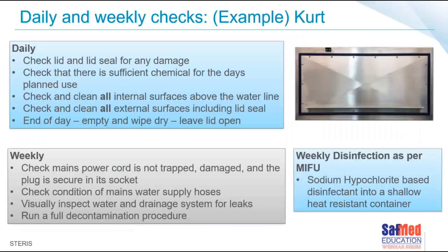Carrying on now with our checks. Right. So looking at this, this is an example of a certain brand's daily and weekly maintenance tasks that need to be carried out to keep the unit performing optimally. So starting with the daily checks, each morning we would want to first inspect that the lid and the lid seal has no damages or wear on it. This will help prevent leaks and ensure proper sealing during the operation. And of course, no aerosols being released.